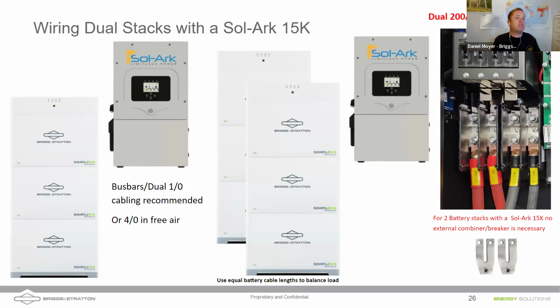Jim is asking if there's any way to reduce the 60-watt standby current when the inverter is idle, maybe keeping it in the shade so the fans aren't working as hard. I've got a Sol-Ark 15k running off a battery stack in my shop right now, and I don't think there's much we can do about that. You do want to make sure it's not hot, but I've noticed the same draw even when the Sol-Ark is idle, keeping everything inside energized. There's some inefficiency present in just about every inverter on the market. I wish there was a sleep mode, but you want to maintain power on your AC bus and load side. For me, if I'm not using it, I just shut it off and leave, which makes sense for an off-grid site when you're away and don't need anything powered. But I don't know of any way to actually reduce that draw.